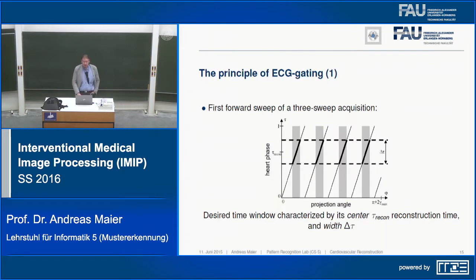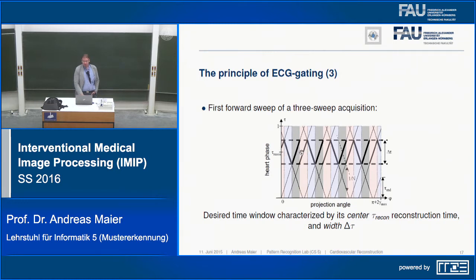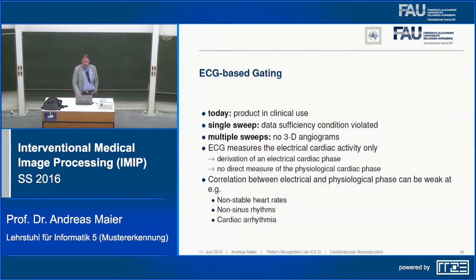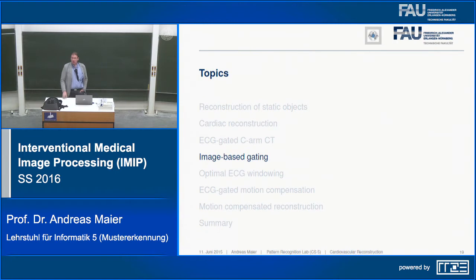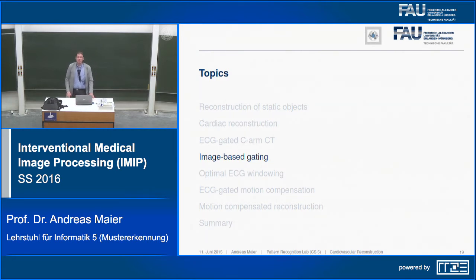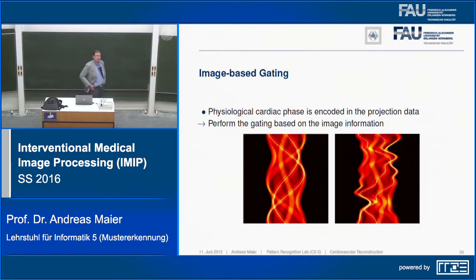The idea from Lauritsch and Fahrig is to create multiple sweeps — rotating the C-arm back and forth — acquiring more and more data of the same heart phase until you cover the entire angular range. You can select these projections for reconstruction, and this is available as a clinical product. However, if the heart is affected by disease, it may not beat perfectly periodically, which is why people came up with additional ideas, including image-based gating.